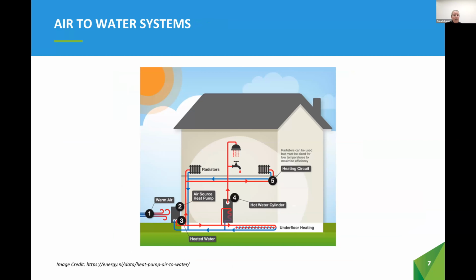There are also air-to-water heat pumps. These transfer heat energy from an evaporator air coil through the refrigerant to a condenser fluid heat exchanger. Heating fluid, typically water or glycol, is then distributed throughout the building through a piping network to the terminal heat transfer units. Terminal heat transfer units could be things like in-floor heating slabs, radiant panels, wall fins, and fan coils. Either way, for all 3 of the units, there will be an outdoor unit that transfers the heat to or from the air. This unit will often look like a typical air conditioner or a condensing unit.